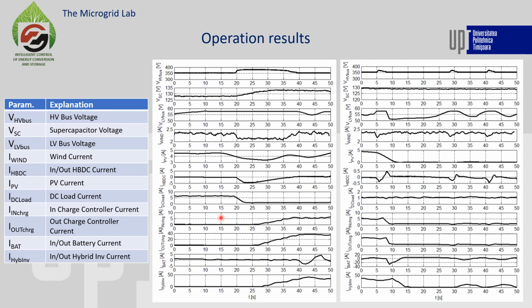When the DC loads receive the command to decrease power consumption, the voltage on the high voltage DC bus rises. As an immediate response, the hybrid bidirectional DC converter goes into charging mode and raises its current in order to charge the supercapacitor. We can see that the voltage on the supercapacitor is increasing.